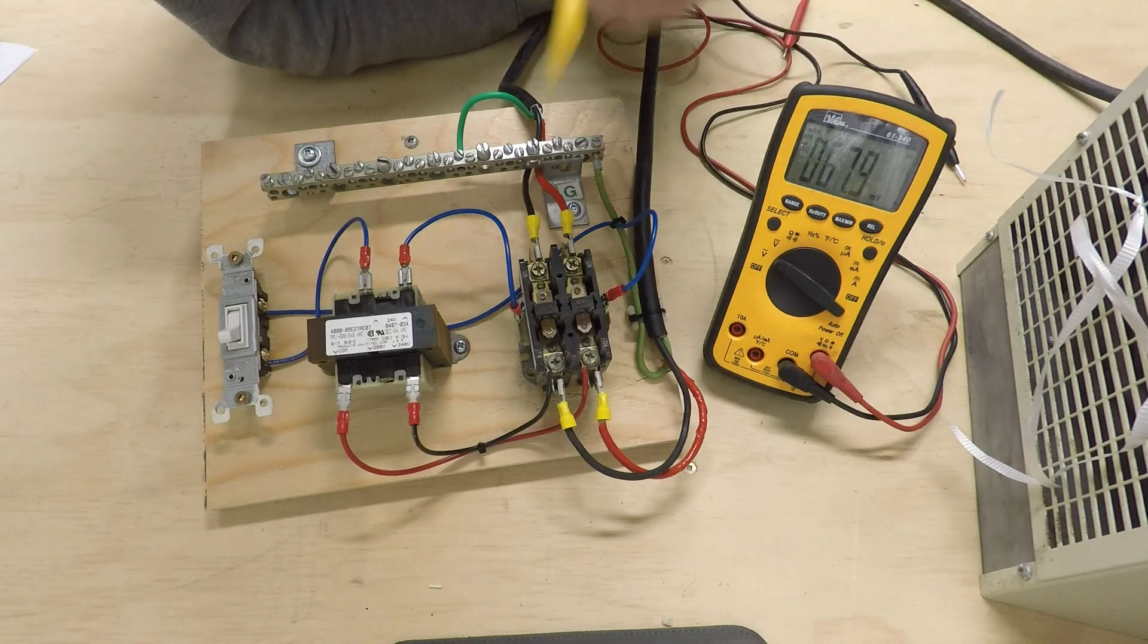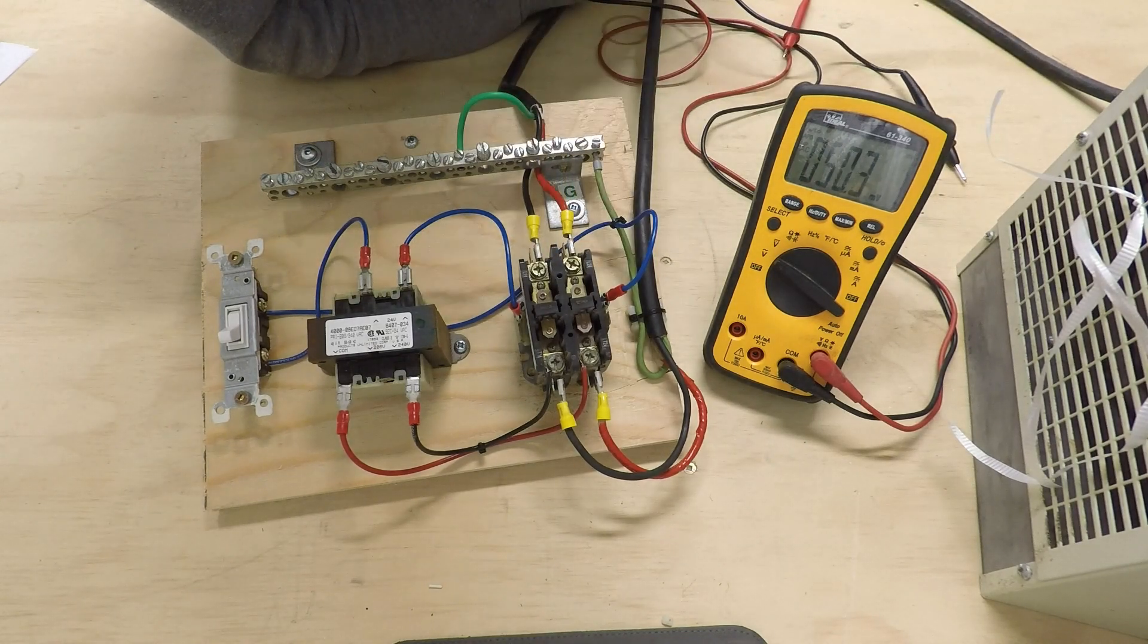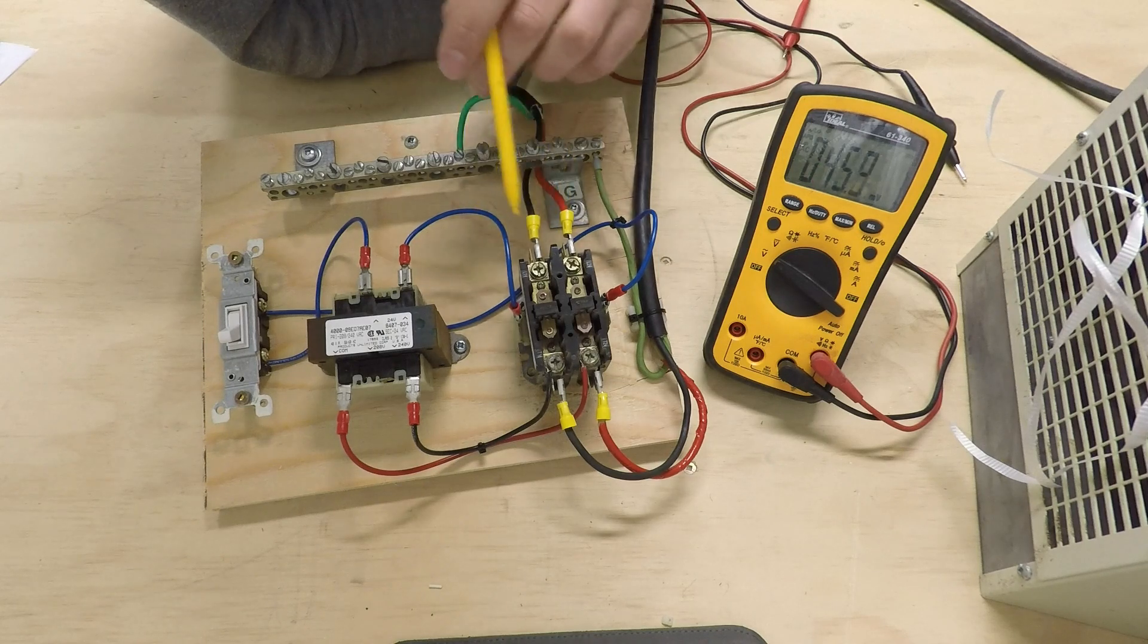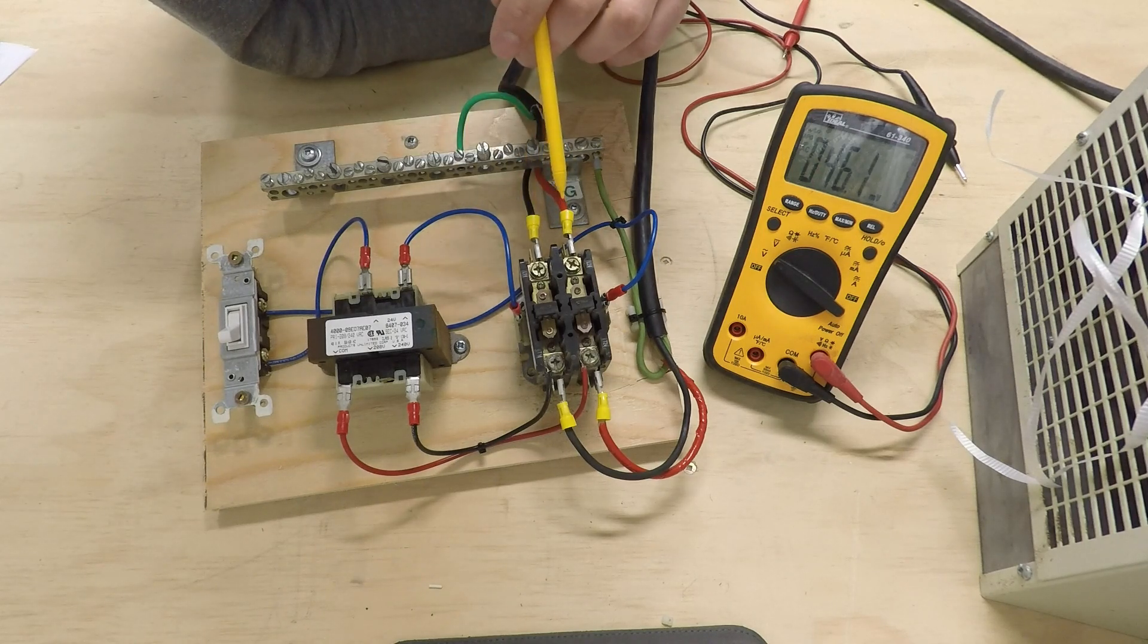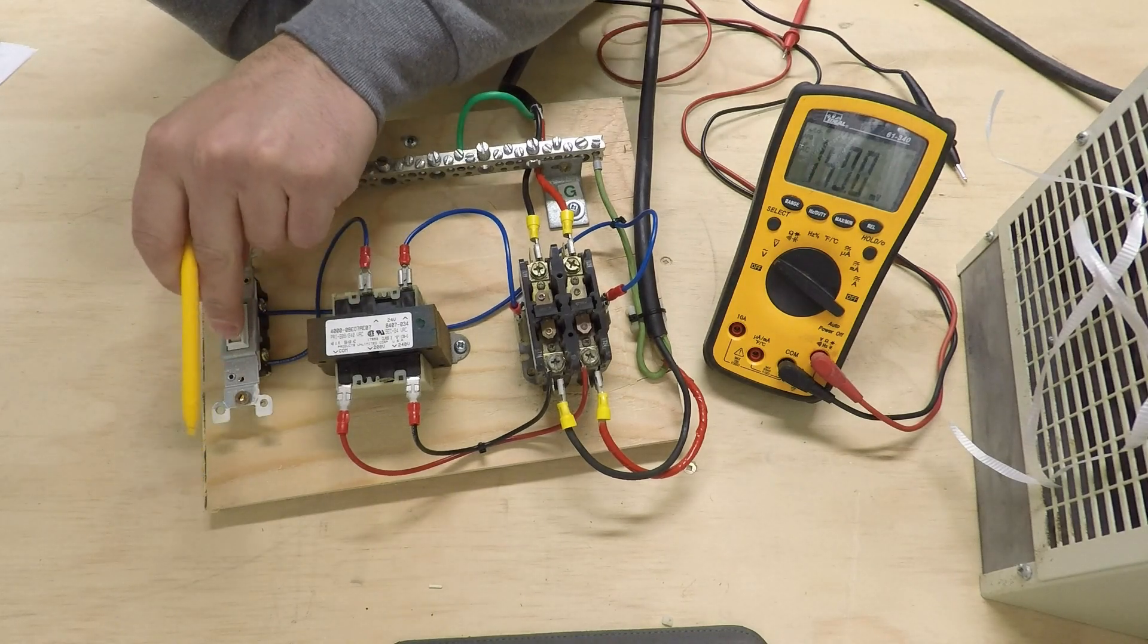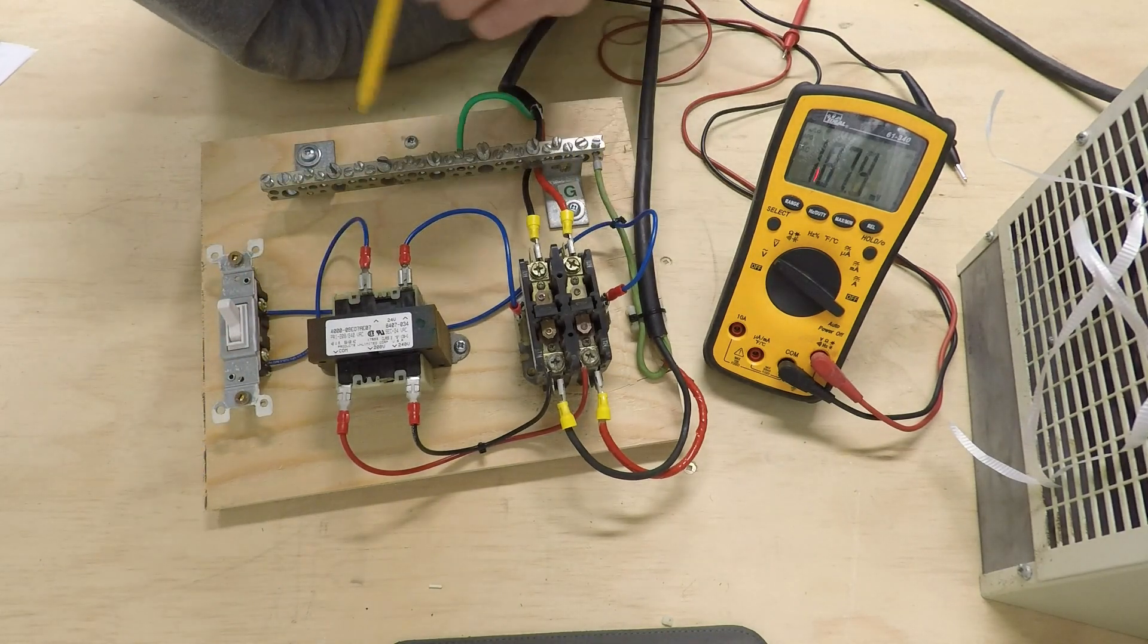So this contactor is actually faulty and I'm going to show you why and a way to troubleshoot to figure out or diagnose the problem. So I'm going to turn it on. You can hear the coil buzzing in the contactor.